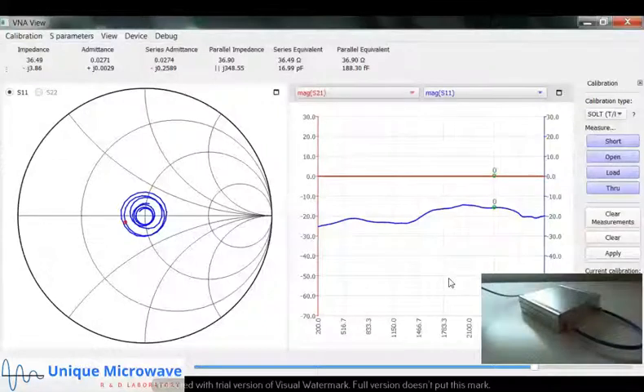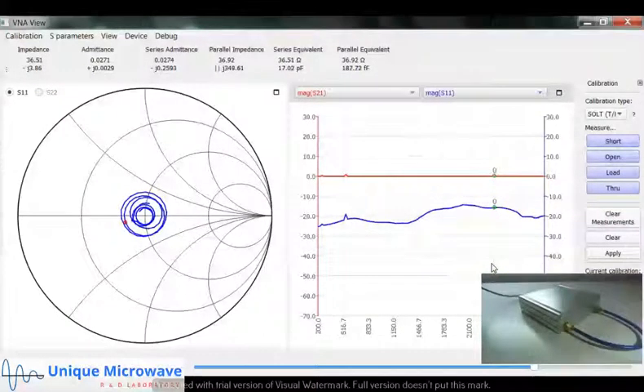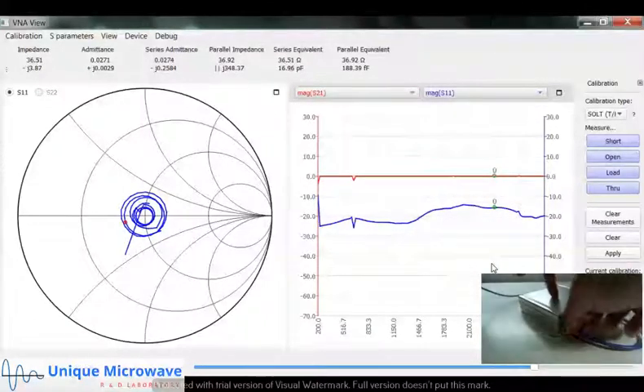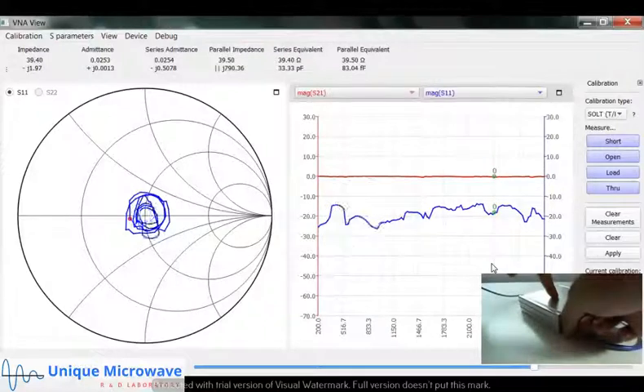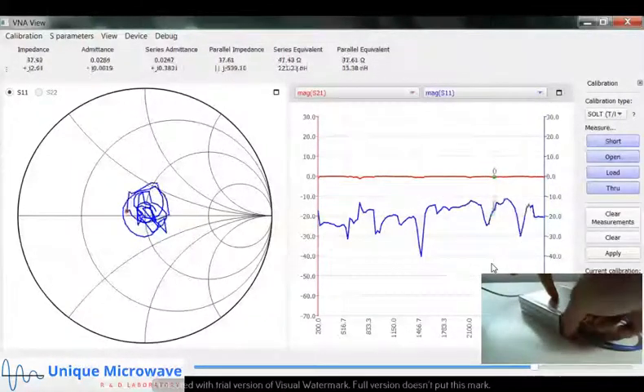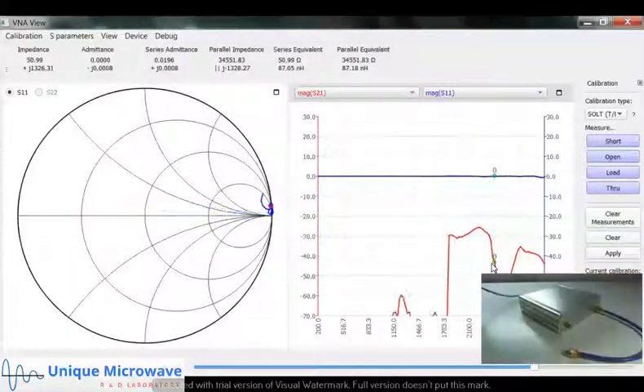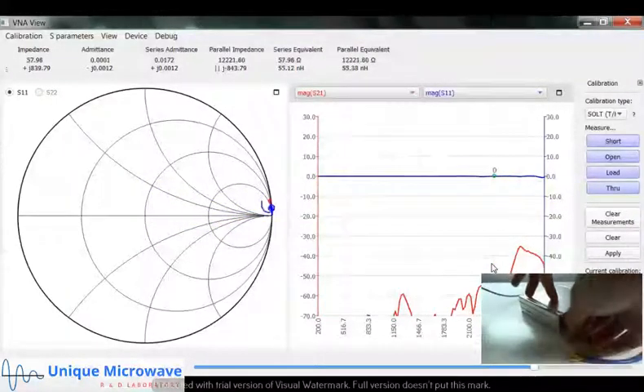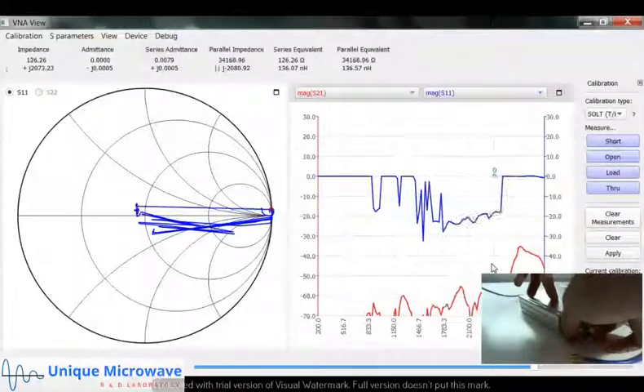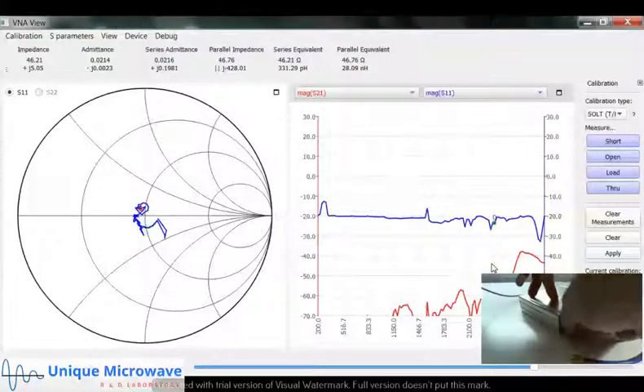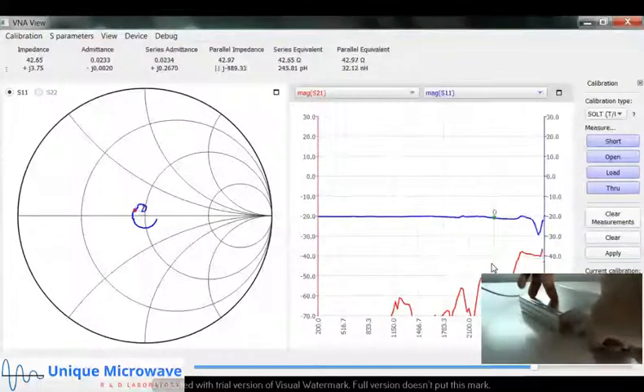In order to test the performance of two-port measurement, we can use a particular kit. For instance, we will be using a 10 dB attenuator. As you can see, this is the 10 dB attenuator. Now, we will need to release the cable from port 1, and then replace it with the attenuator. Subsequently, connect the end of the attenuator with the cable.